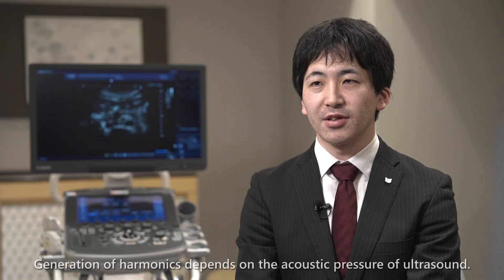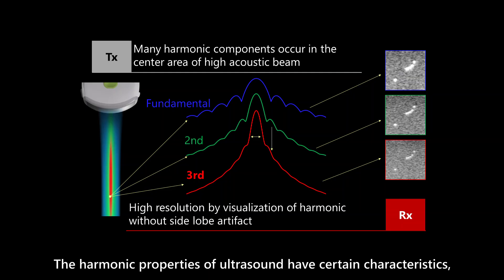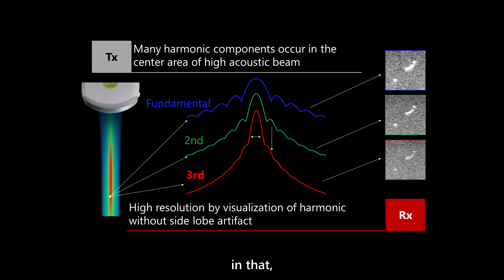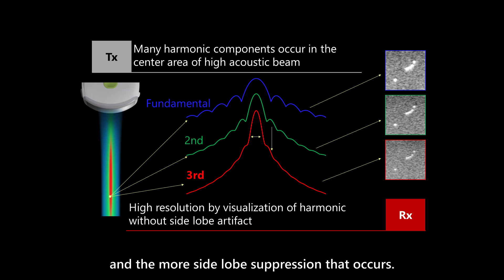Generation of harmonics depends on the acoustic pressure of ultrasound. The harmonic properties of ultrasound have certain characteristics in that the higher the order of harmonics, the thinner the main beam becomes, and the more side lobe suppression that occurs.